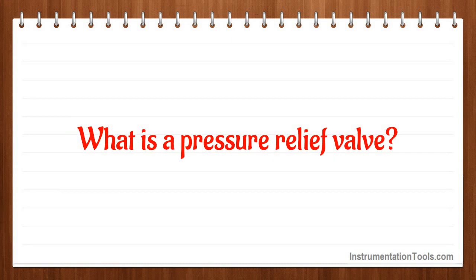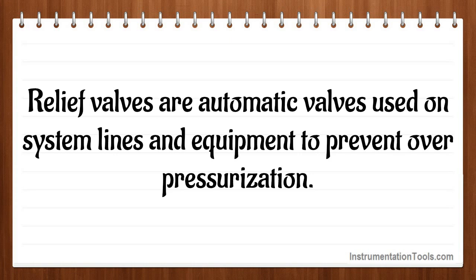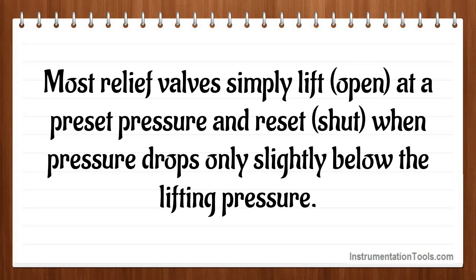What is a pressure relief valve? Relief valves are automatic valves used on system lines and equipment to prevent overpressurization. Most relief valves simply lift open at a preset pressure and reset shut when pressure drops only slightly below the lifting pressure.